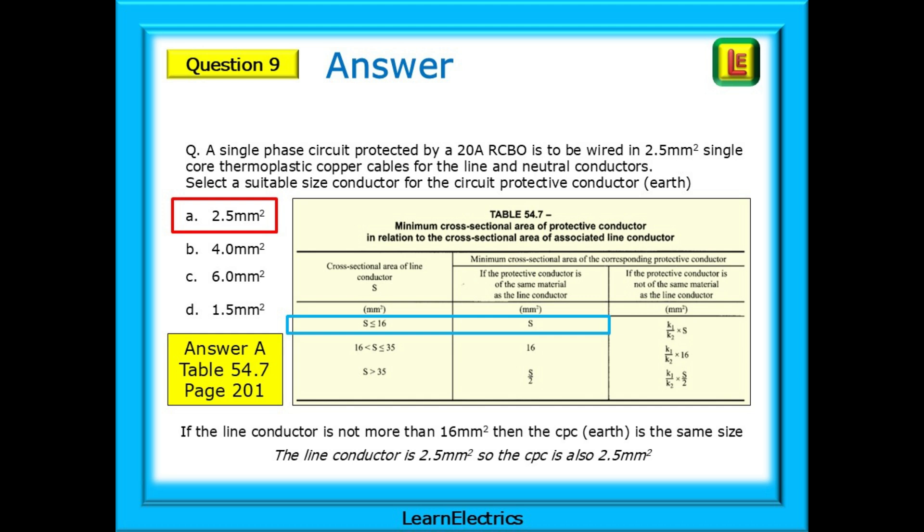The answer is choice A, 2.5 square millimetre single conductor. This is found by using table 54.7 on page 201. If the line conductor is not more than 16 square millimetres, then the CPC or earth is the same size as the line conductor.